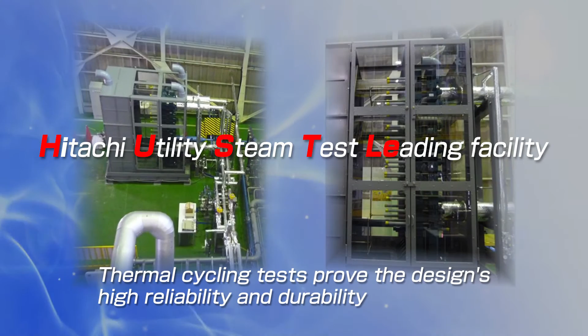Hitachi GE Nuclear Energy's Hustle facility was employed to demonstrate the Hestia NX-50. Hustle is a thermal hydraulic test facility that can replicate the actual operating conditions encountered in nuclear generating stations. The Hestia NX-50 also demonstrated superior performance while undergoing thermal cycling. The Hestia NX-50 proved itself when subjected to thermal cycling between 182 degrees Celsius and room temperature. These temperature swings are representative of challenging reactor shutdown cooling operations.